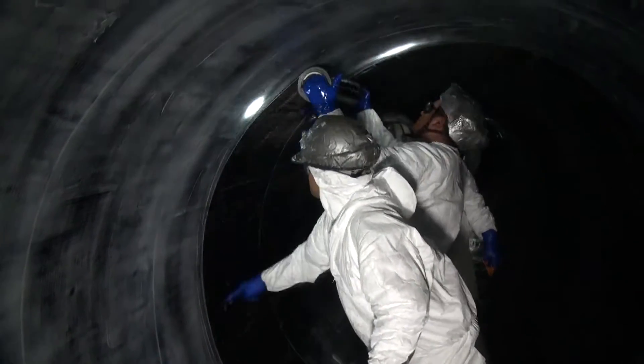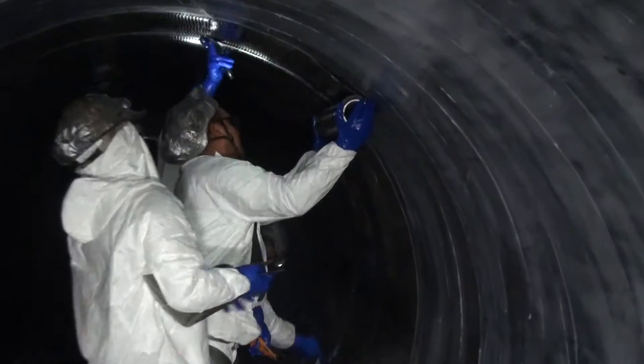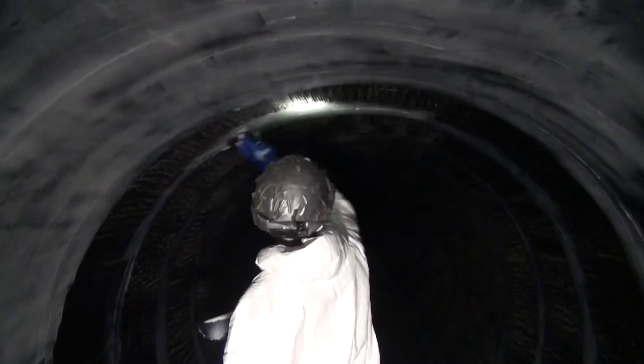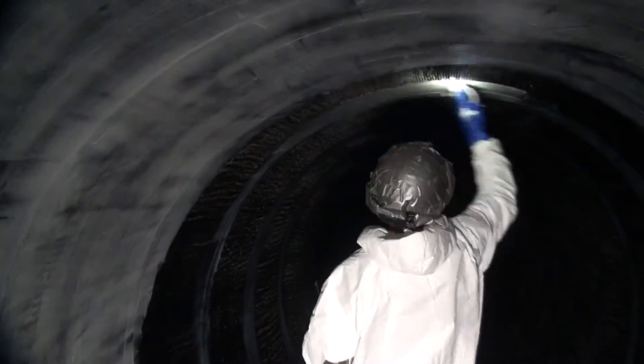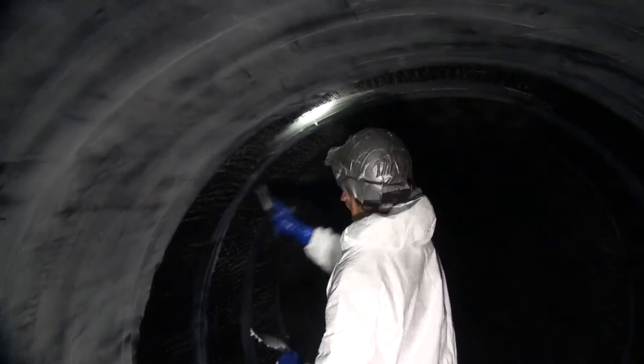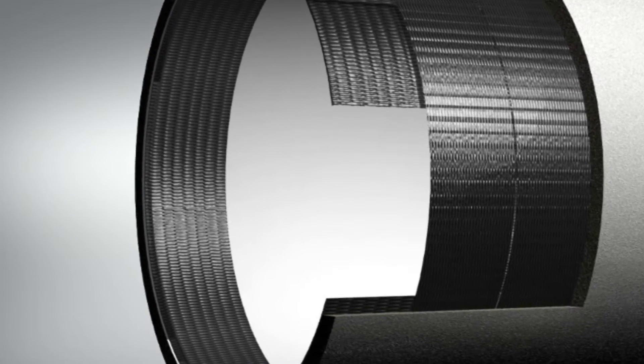One trenchless method used widely across the United States for high-pressure large diameter pipelines is carbon fiber reinforced polymer. This lightweight, high-strength material is installed on the interior of distressed pipeline segments and provides a full structural upgrade, able to resist all internal pressure and external loads. Structural Technologies' V-Wrap carbon fiber is an approved system for Miami-Dade pipelines.